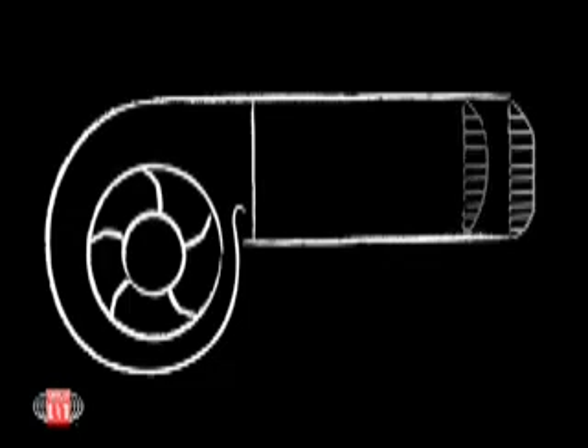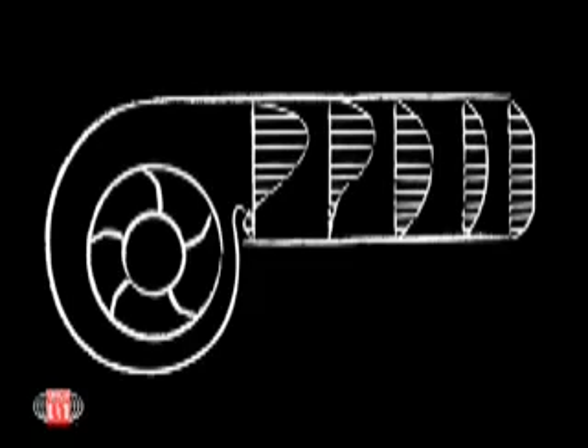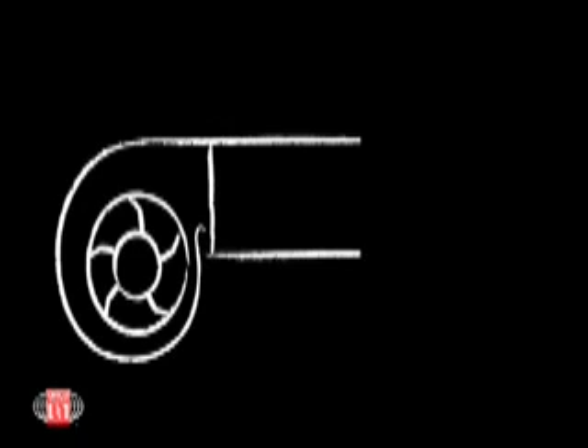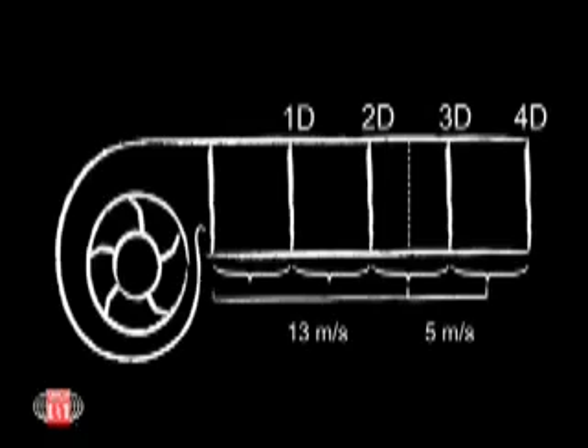Ducting on the outlet needs to be designed so that the asymmetrical flow profile from the fan is allowed to diffuse and approach fully developed flow. The point where this is achieved is referred to as 100% effective duct length. A good rule of thumb is that effective duct length is 2.5 duct diameters when duct velocity is 13 meters per second or less, with 1 duct diameter added for each additional 5 meters per second.